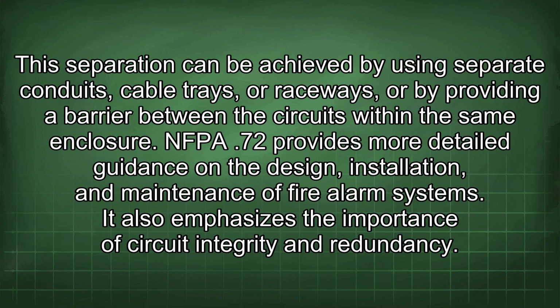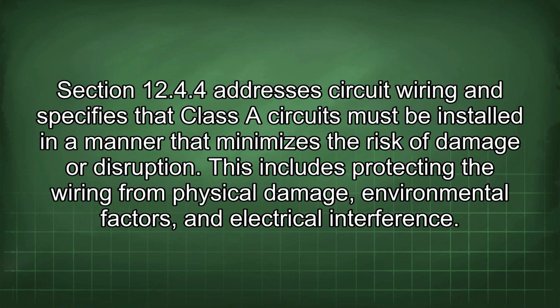NFPA 72 provides more detailed guidance on the design, installation, and maintenance of fire alarm systems. It also emphasizes the importance of circuit integrity and redundancy. Section 12.4.4 addresses circuit wiring and specifies that Class A circuits must be installed in a manner that minimizes the risk of damage or disruption. This includes protecting the wiring from physical damage, environmental factors, and electrical interference.